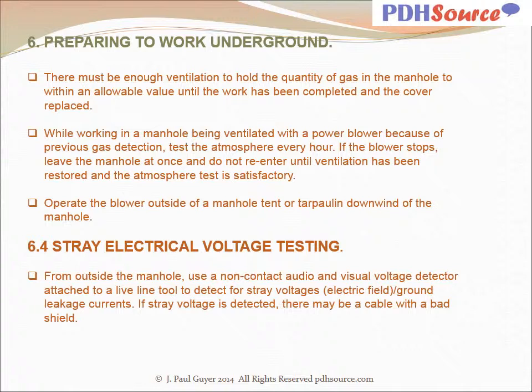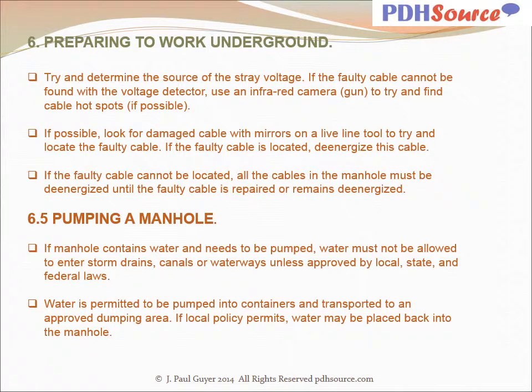With regard to stray electrical voltage testing, from outside the manhole, use a non-contact audio and visual voltage detector attached to a live line tool to detect for stray voltages, electric field, ground leakage currents. If stray voltage is detected, there may be a cable with a bad shield. Try and determine the source of the stray voltage. If the faulty cable cannot be found with the voltage detector, use an infrared camera gun to try and find cable hotspots if possible. If possible, look for damaged cable with mirrors on a live line tool to try and locate the faulty cable.